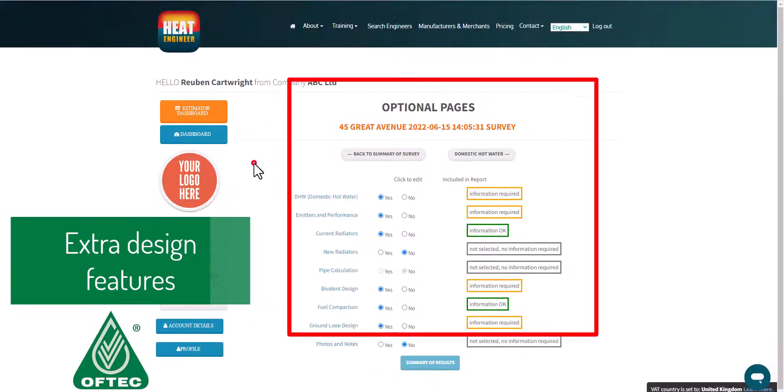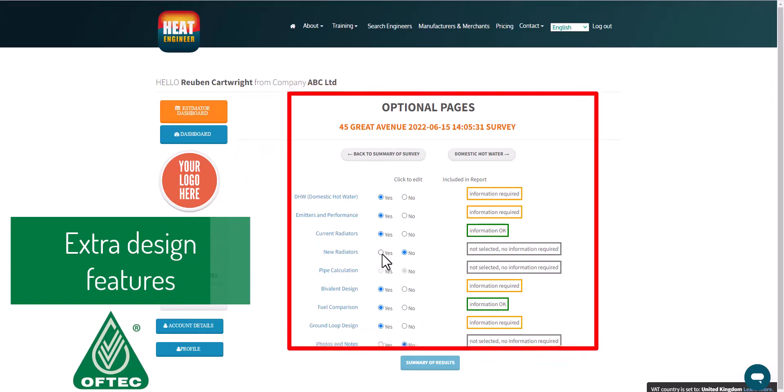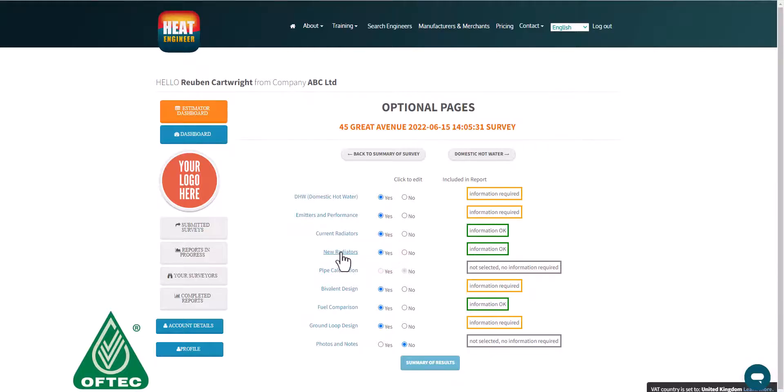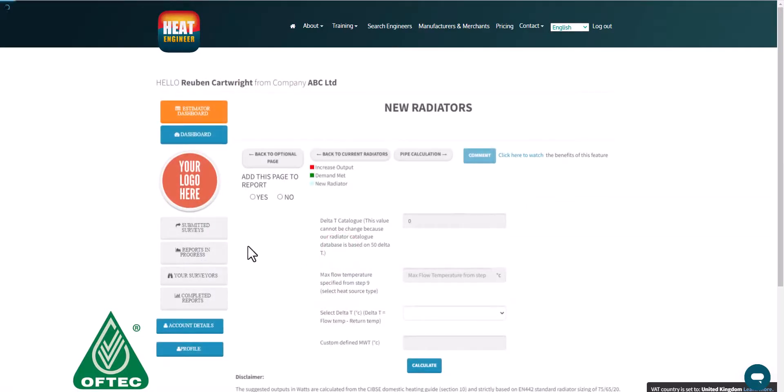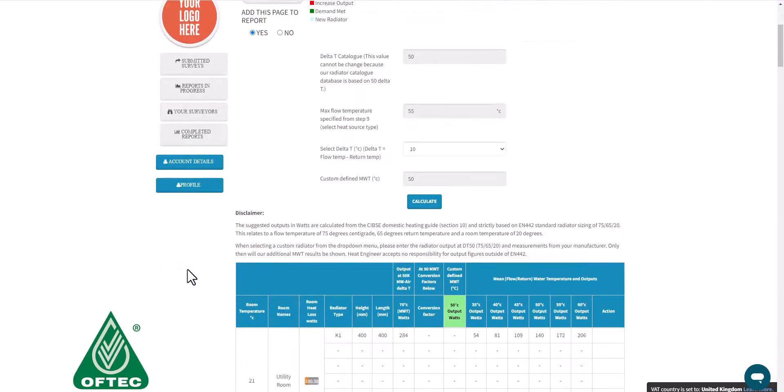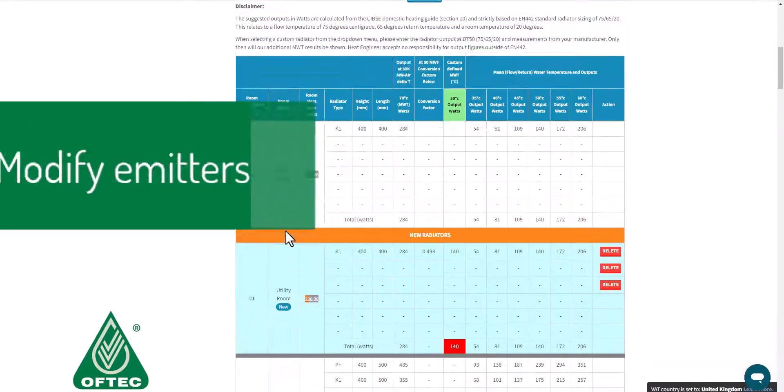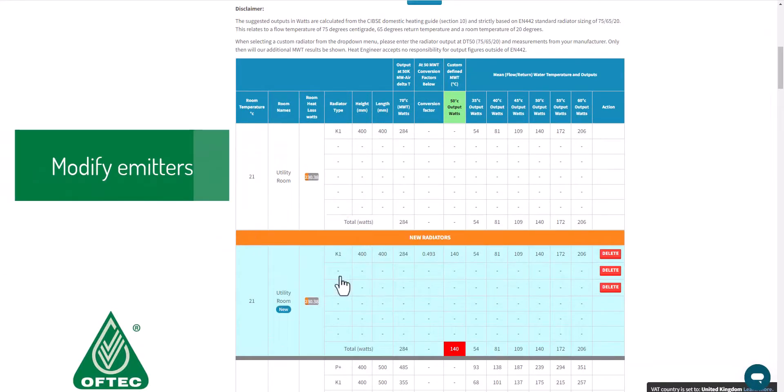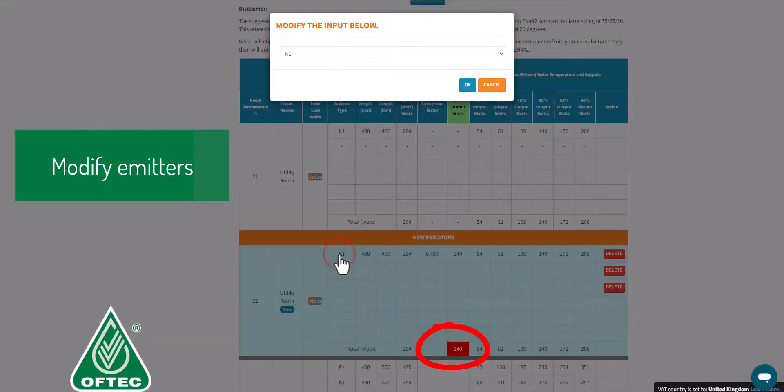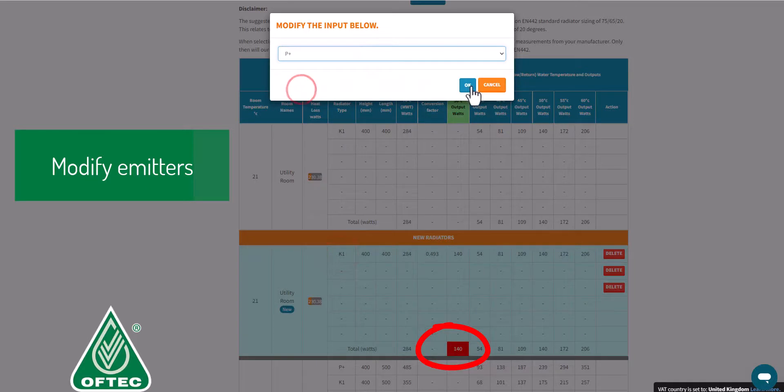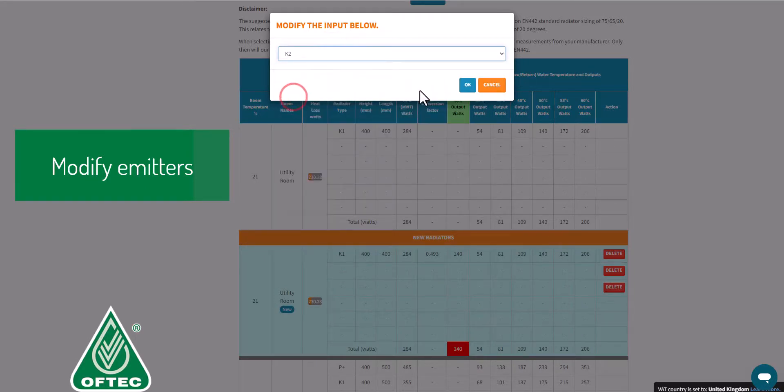Once we're happy with that, we go into the optional pages. Within here there's lots of flexibility so we can design our new radiators, we can specify them at a given flow temperature and delta t. The software will actually inform you if the current radiator is not adequate. In this case the cell is highlighted red, and we can select from the drop down just to experiment with different radiators until that cell turns green.